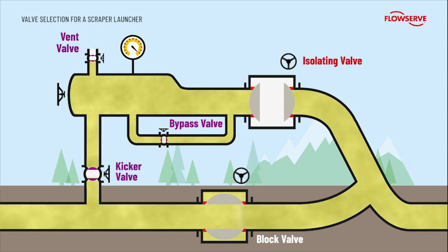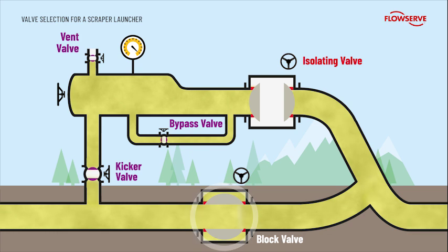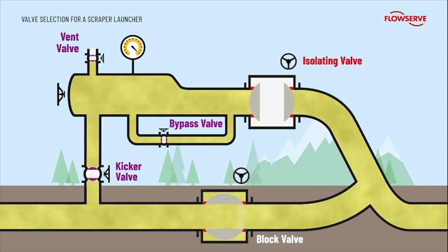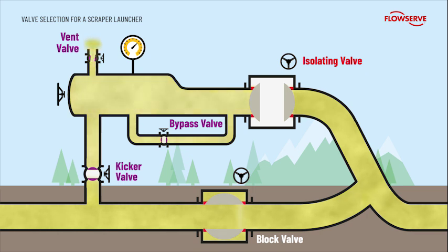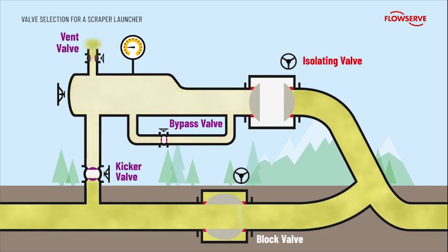At the start of the launching sequence, all valves are closed except the block valve. The gas is flowing in the pipeline at high pressure and the launcher station is isolated. To begin the procedure, the launcher chamber is depressurised by opening the vent valve into the atmosphere. A soft-seated ball valve would be damaged during a full differential pressure opening. Therefore, a plug valve is used to ensure that isolation to the atmosphere is restored once the valve is closed.